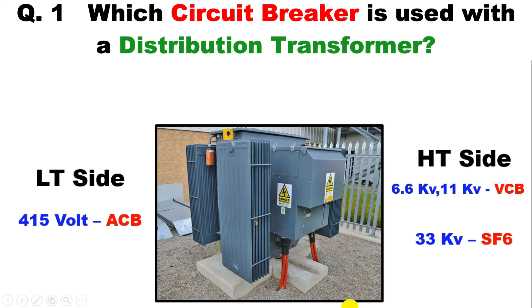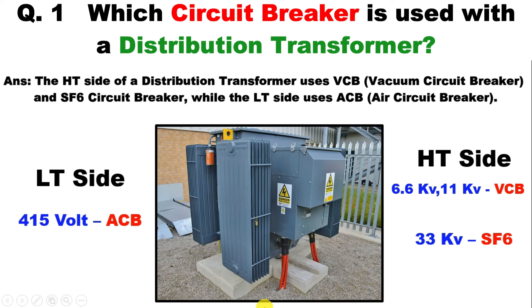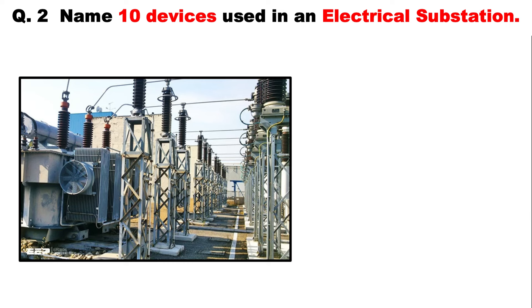So how do you give the answer? You should say: for the HT side of a distribution transformer, VCB or SF6 circuit breaker is used. For the LT side of the transformer, through which we distribute power supply, we use an ACB.